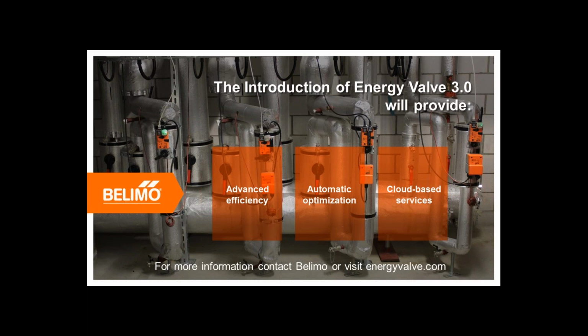Can we use the energy valve across the chiller inlet outlet to increase delta T in production? Across the chiller inlet and outlet. I don't know necessarily that you would want to install it on the inlet and the outlet. You could certainly use it on one side of the chiller.